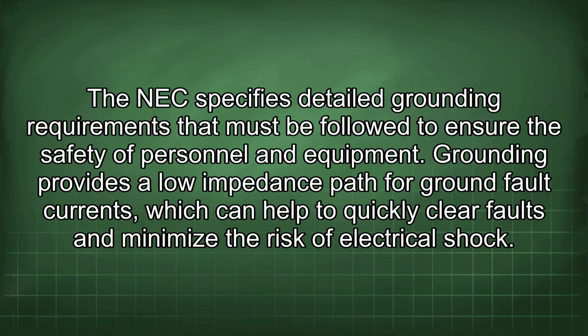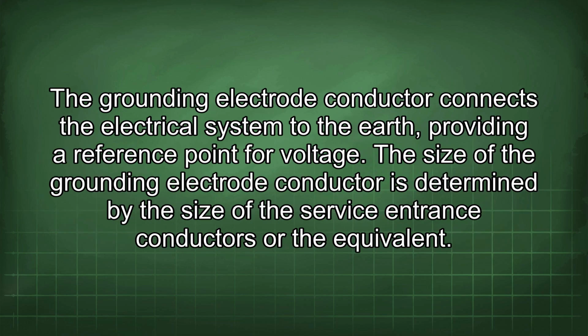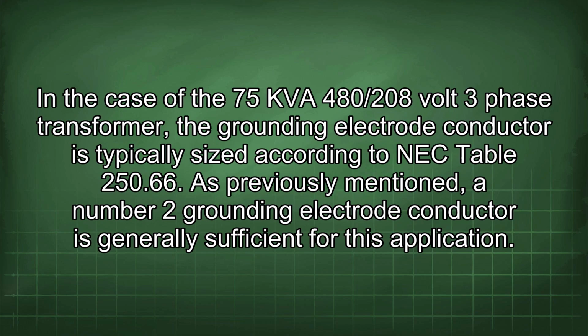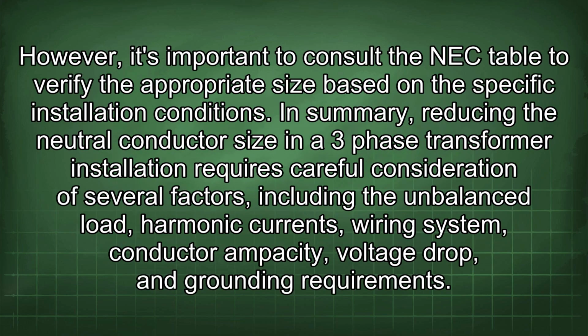Grounding provides a low impedance path for ground fault currents, which can help to quickly clear faults and minimize the risk of electrical shock. The grounding electrode conductor connects the electrical system to the earth, providing a reference point for voltage. The size of the grounding electrode conductor is determined by the size of the service entrance conductors or the equivalent. In the case of the 75 kVA 480/208 volt three-phase transformer, the grounding electrode conductor is typically sized according to NEC Table 250.66. As previously mentioned, a number 2 grounding electrode conductor is generally sufficient for this application. However, it's important to consult the NEC table to verify the appropriate size based on the specific installation conditions.